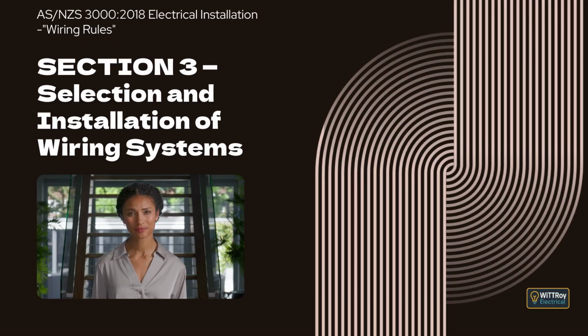Clause 3.3.2.12 Hazardous areas. This clause states that wiring systems installed in areas with explosive gas or explosive dust atmospheres must be selected and installed in accordance with the relevant hazardous area requirements. Clause 3.3.2.13 Thermal insulation. This clause explains that where cables pass through bulk thermal insulation, their current carrying capacity must be rated according to the length of cable within the insulation. Short lengths up to 150 mm use the in-air rating, longer lengths up to 400 mm use the partially surrounded rating, and lengths greater than 400 mm use the completely surrounded rating.